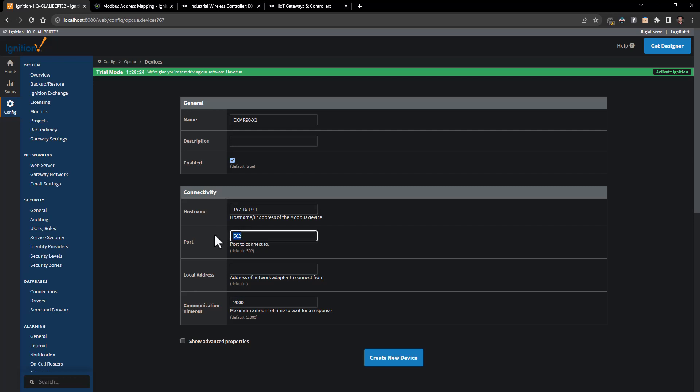We're going to stay on port 502. If you have a special network adapter you'd want to put that information in here, and we can adjust what we want our timeout to be. There's also a number of advanced properties that you can adjust and play around with, but in this case we really don't need to adjust any of those for a standard setup.